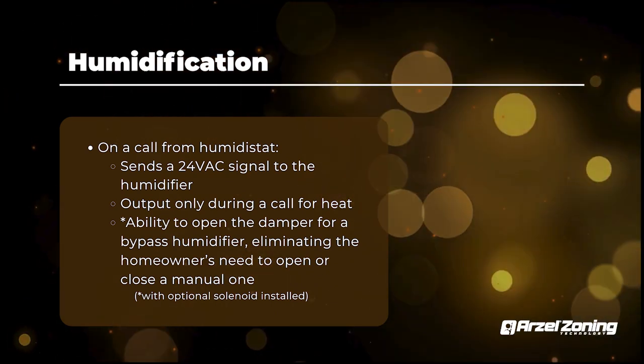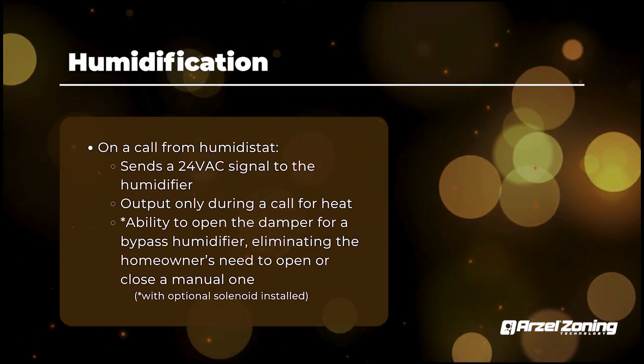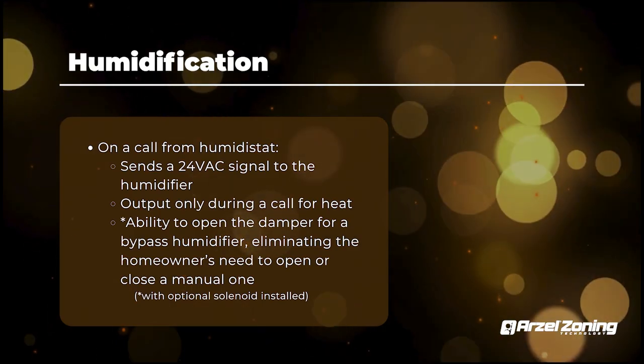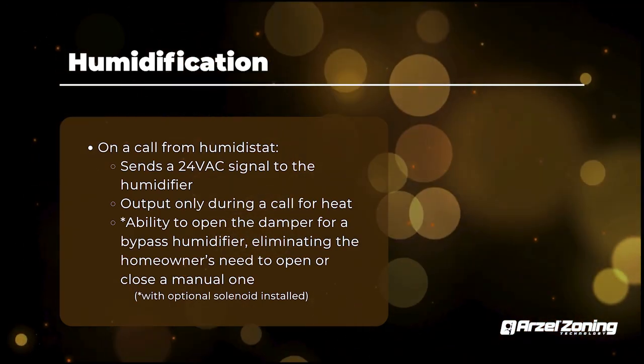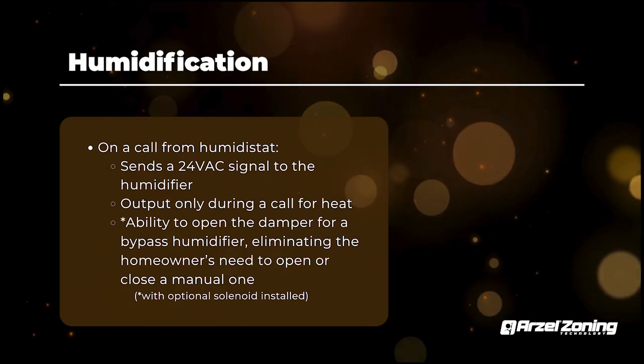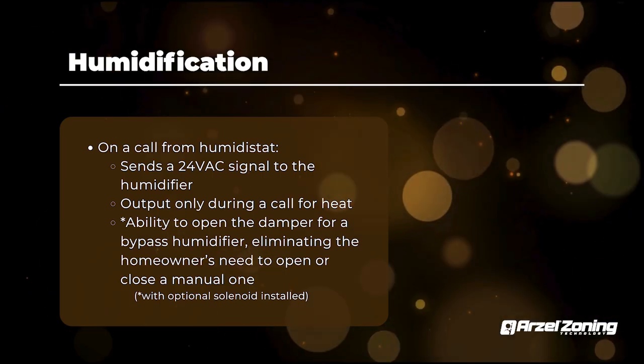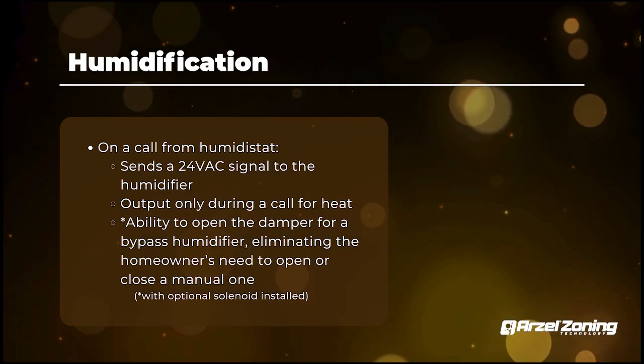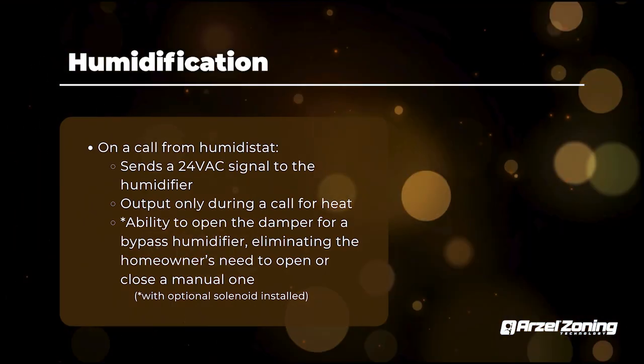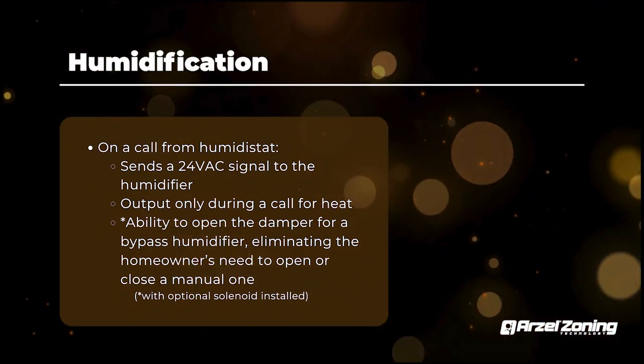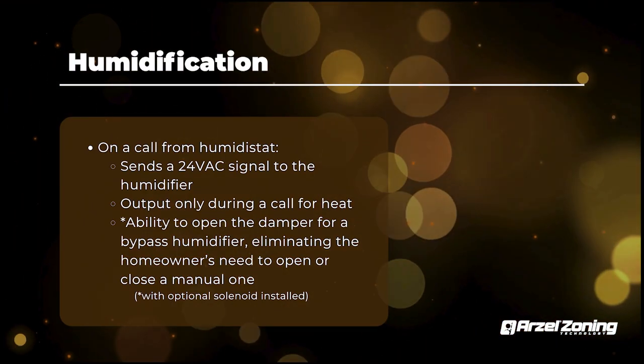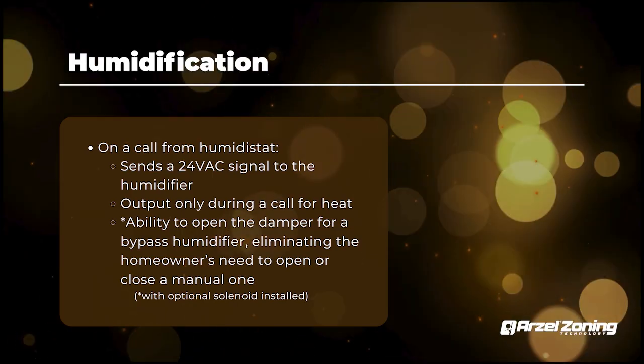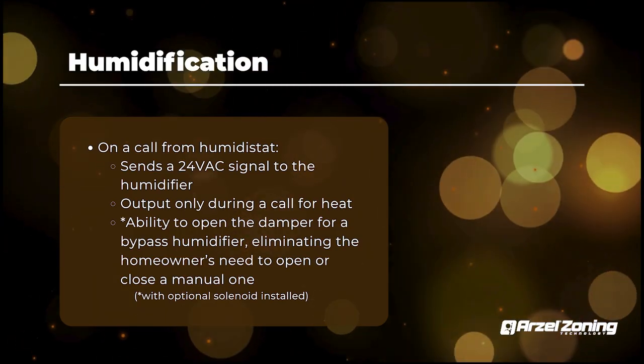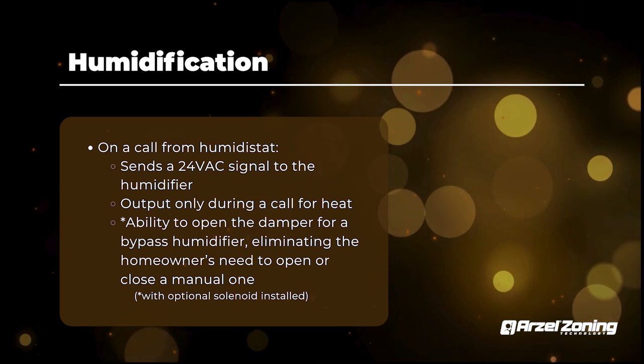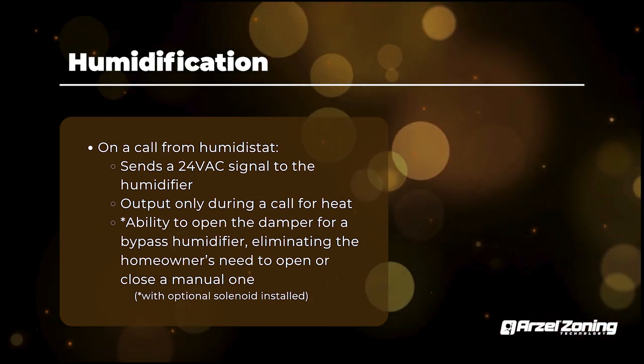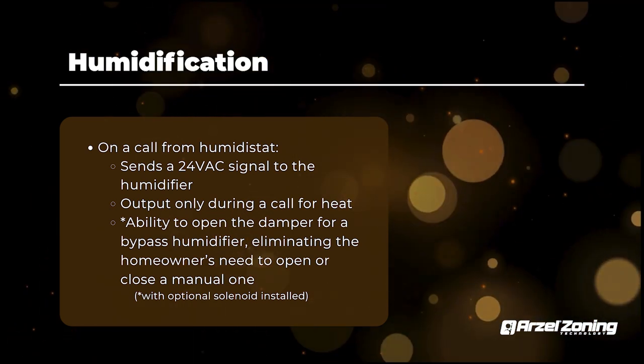And if there's no call on the Arzel panel, all of our dampers are in the open position. So you would get that whole house humidification. And then if there is a call on an opposing zone, you're just going to close those zones off and just humidify the area that's actually calling at that time. And then once your zones are satisfied again, it would reopen the dampers and continue humidifying the whole home. So if you guys want blower activation, that's your better route. If you don't mind just running it with a heating call, you're more than welcome to use it.